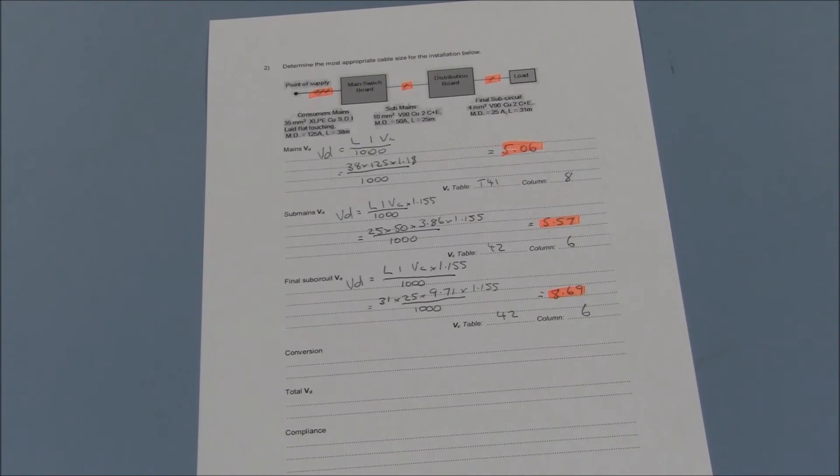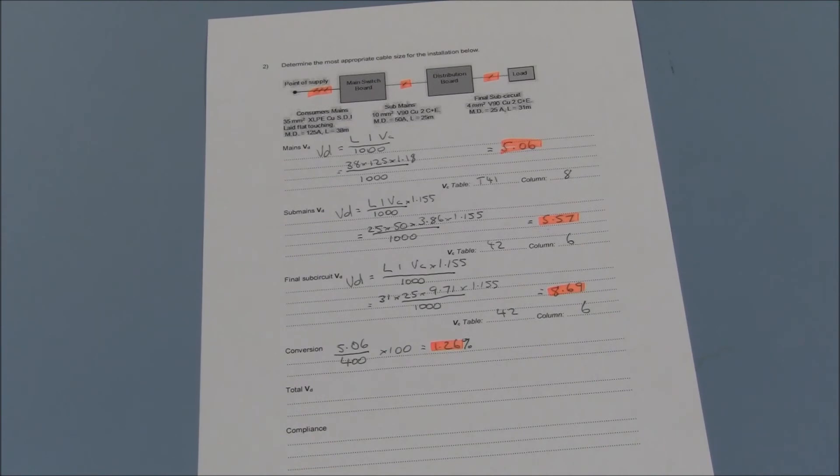We can now start translating these values into percentages of the relevant voltages. For the consumers mains, we had a drop of 5.06 volts. That drop is 1.26% of the supply voltage of 400 volts.